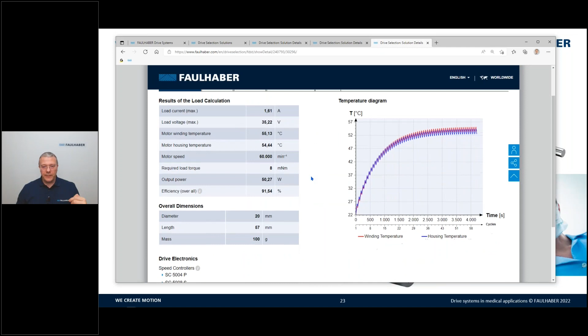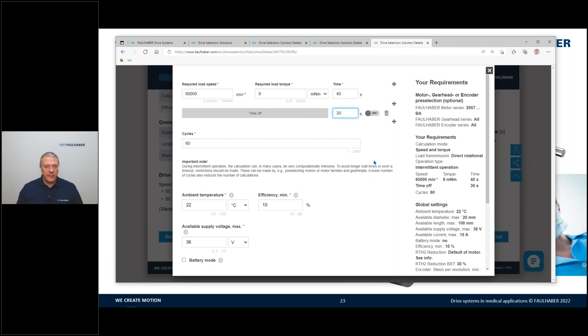If you want to change or modify an input value with the chosen motor, you have that option. If you want to increase this to 9 millinewton meter and decrease the timing to 30 seconds like this, you can recalculate with the new data and see the new results. The motor housing temperature was 54, now it's 53 degrees, and so on.